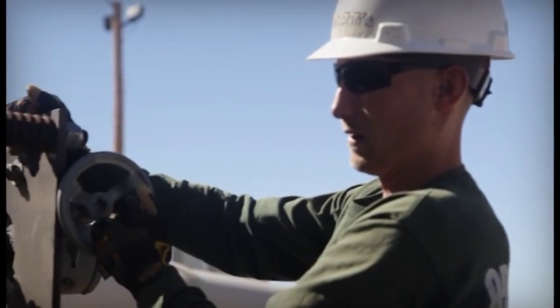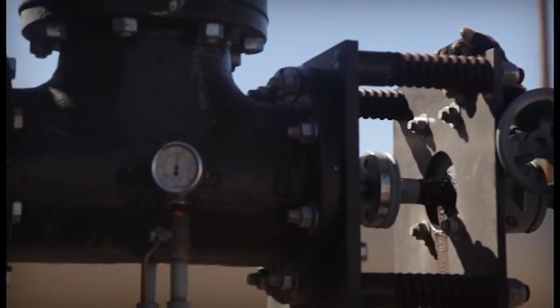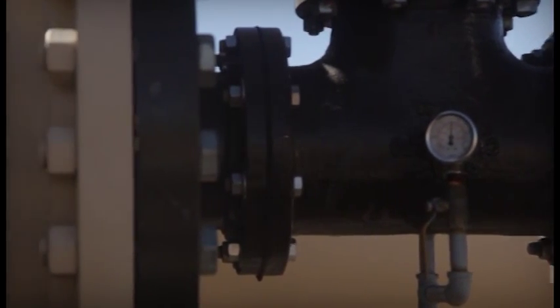The sudden release of pressure by means of a back pressure control valve causes the dissolved air to come out of solution and form microscopic bubbles. These microscopic bubbles adhere to incoming solids and form a buoyant blanket which rises to the surface for mechanical removal.